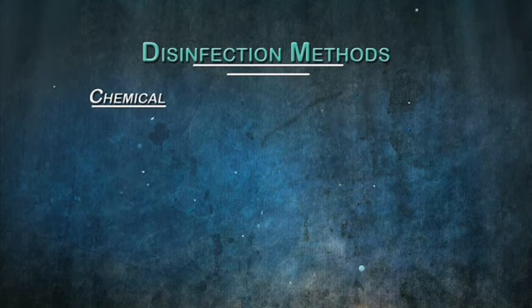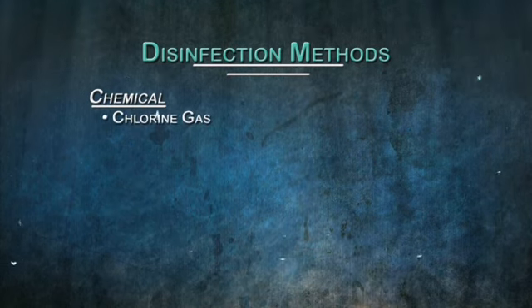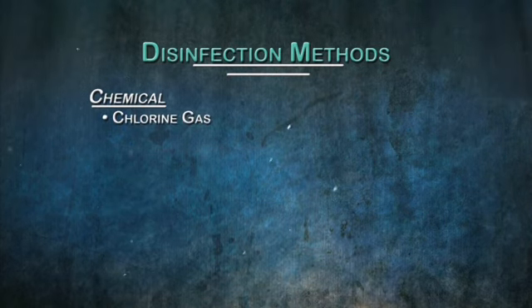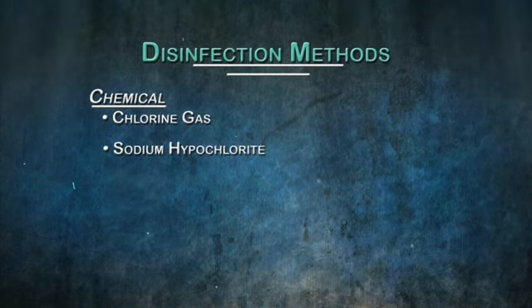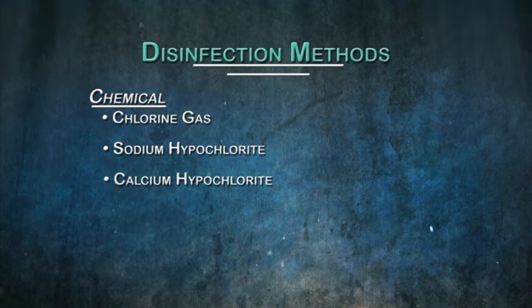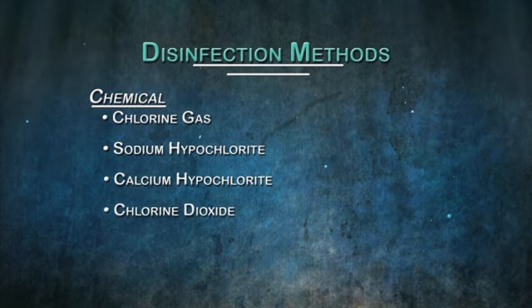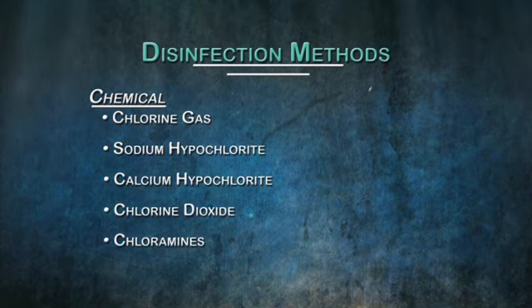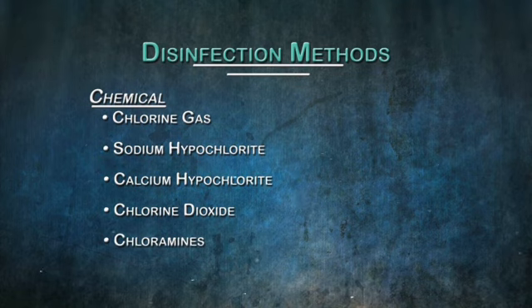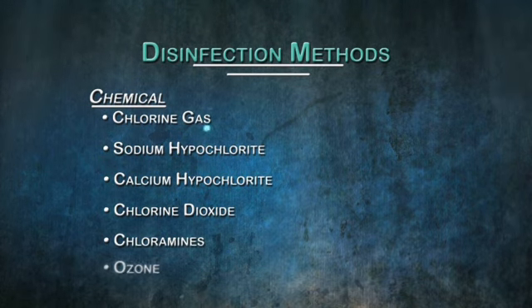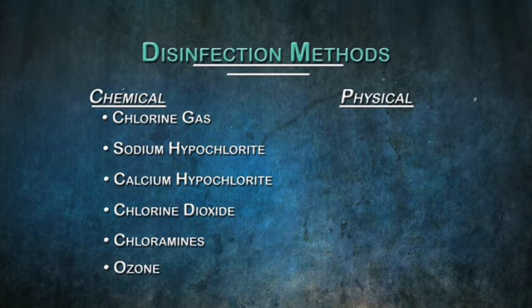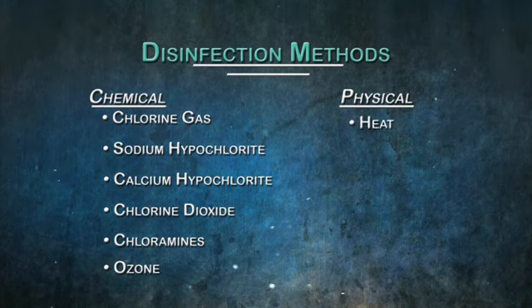Utilities that disinfect can use a number of methods, some chemical and some physical. Examples of the chemical methods include chlorination with chlorine gas, sodium hypochlorite, calcium hypochlorite, chlorine dioxide, or chloramines, which are made by combining chlorine and ammonia, and disinfection using ozone. Examples of the physical methods include heat and ultraviolet radiation.